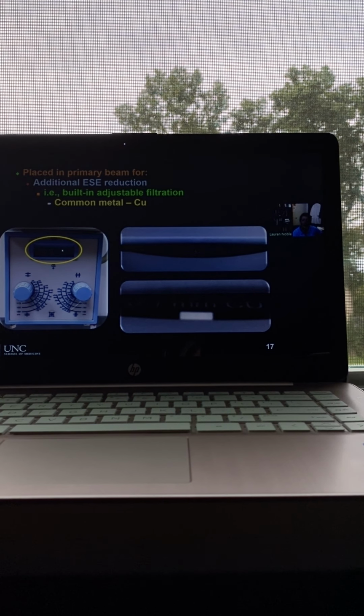There's a dial, I don't know if you all noticed, but there's a dial up above the collimator knobs here. And we're going to do an experiment with this tomorrow, so we'll play around with this tomorrow. But when you look at the dial, it has numbers on it. Typically, we leave it in the 0 position because we don't want any extra filtration in the beam, typically, for the experiments that we end up doing in lab, okay?